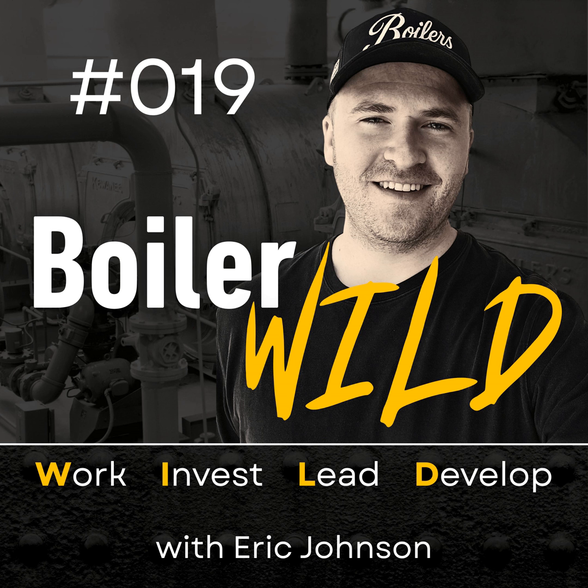So, if you are new to the condensing boiler market, a condensing boiler is something that is kind of new to the boiler industry. I wouldn't say it's new, but it's within the last 20 to 30 years that condensing boilers have reached the market and become popular, and that is due to saving energy and the higher energy prices and a lot of government rebates for reducing emissions. And we want to make the world a cleaner, better place. So manufacturers started coming out with a condensing boiler, and a condensing boiler is different than a non-condensing hydronic boiler in the fact of how the heat exchanger is built.